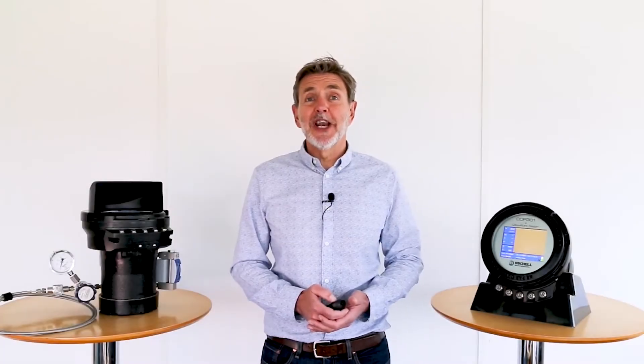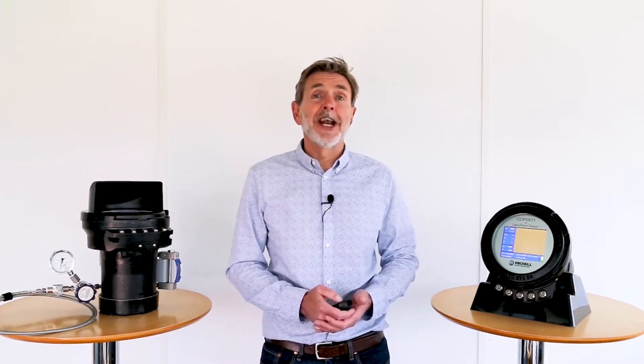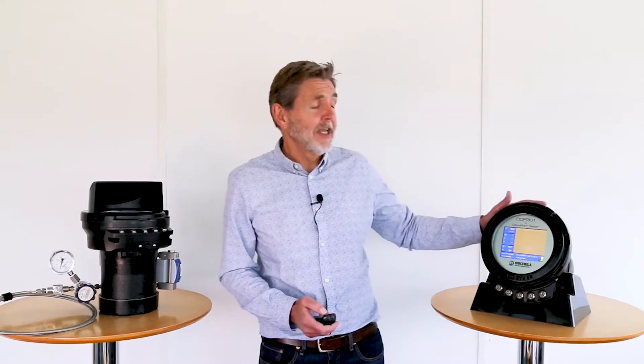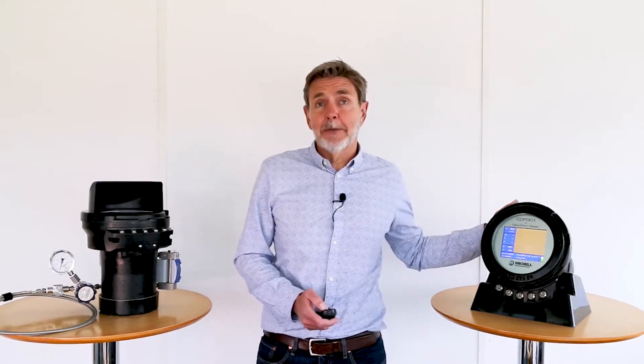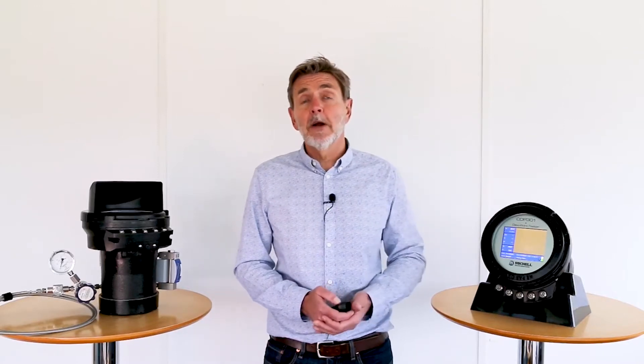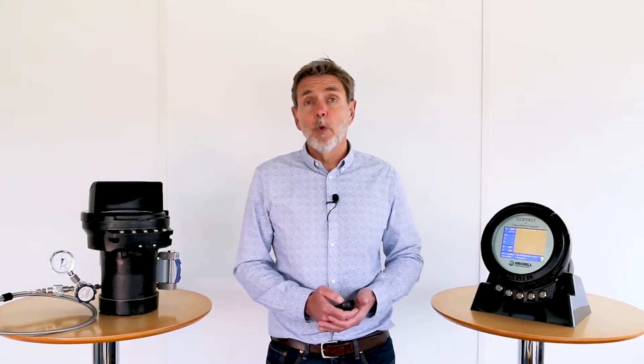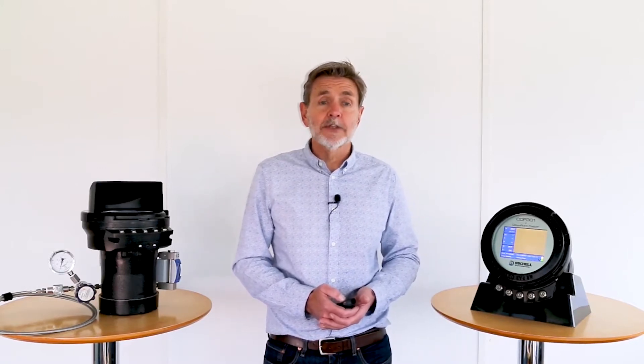This video introduces the latest new product from Michell Instruments for the measurement of water and hydrocarbon dew point in natural gas: the CDP301 Condumax dew point tester. CDP301 is a fully self-contained battery powered portable instrument. It applies the cooled mirror or chilled mirror measurement principle to derive both hydrocarbon and water dew point in natural gas.